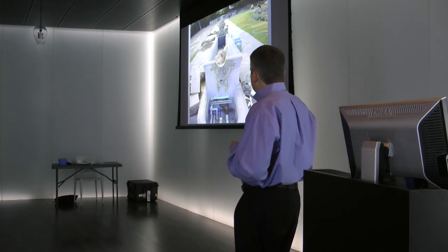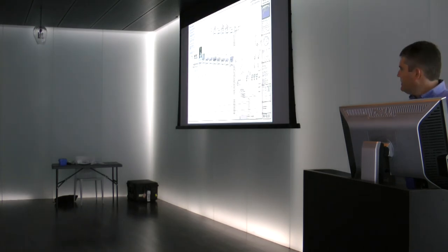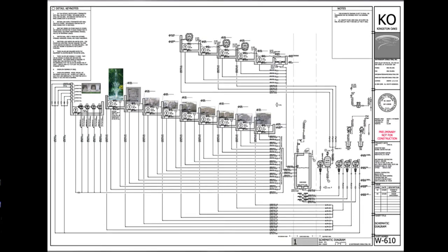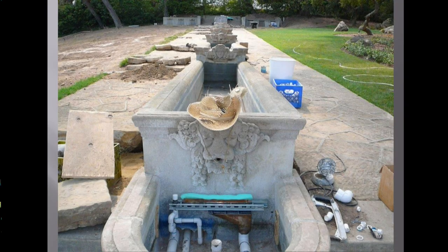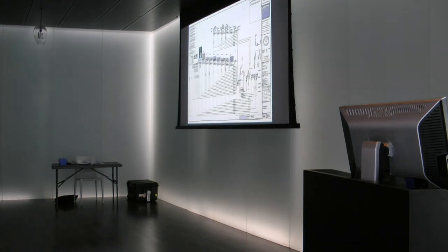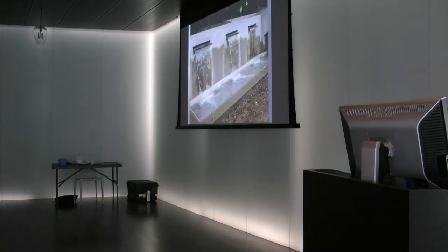What we did is we put in a tank underground and multiple pumps, and we pulled out of the tank, and we fed each of those mouths independently with clean filtered water. And then we had a skimmer, basically a custom bronze piece that I designed, which really just had a little slot. So as this water would fall over, it would overflow here, and all that water would flow by gravity back to the tank. So each system was sort of its own independent little vessel, but all shared a common tank, a single set of filtration and chemical treatment systems. And we were able to adjust the flows going to each different vessel.